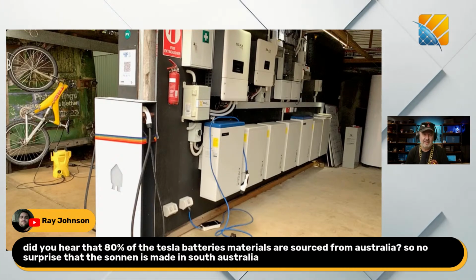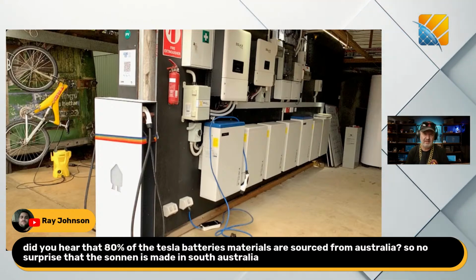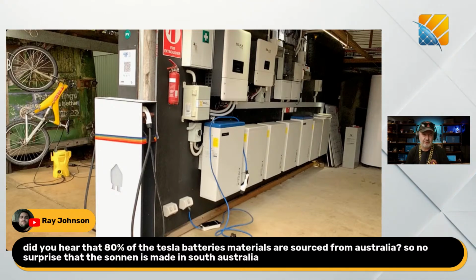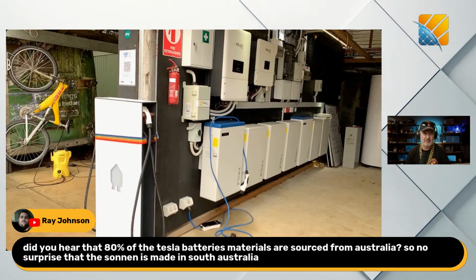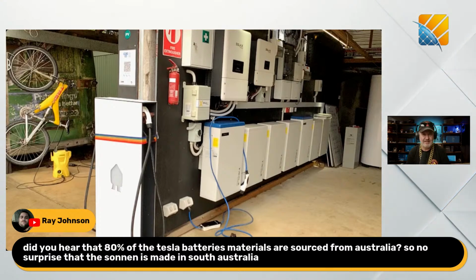The reason I say that they're really an on-grid product is products designed for off-grid often have a couple of extra criteria that, in my mind, make them suitable. One is that they have the ability to auto-start a generator. So they need some form of voltage-free contacts that can be used with a 2-wire start to an auto-start generator, turn it on when required. So reliable power irrespective of solar and battery state. But most hybrid inverters don't need that and don't have it.